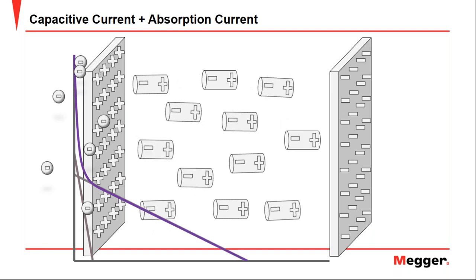Okay, now let's see how these four currents interact with each other and how we should do the insulation resistance test in order to be sure that we are making the measurement with the important current, the one that interests us, and that is the leakage current. Taking into account that the total current is the sum of the four that we saw previously, when adding the capacitive and the absorption current, we have a result like the one shown in the animation, where the high initial value of both currents is evident, and also how they discharge over time. They both have a very high value, and over time, they are discharged to ground.